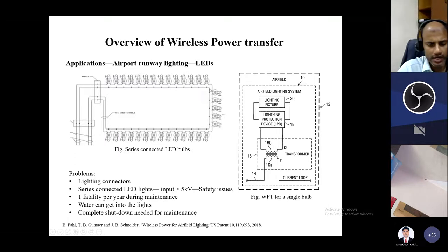An airport runway could be as long as 2 kilometers or more. On both sides of the runway there are LEDs, and the requirement is that all the LEDs be connected in series so they get the same amount of current and glow the same, which means the input voltage will be very high—given as 5 kilovolts or more. This creates safety issues when people do maintenance on the system, with a possibility of electrocution, and one fatality per year during maintenance is reported. Water can also get into the lights, along with the high voltage, and that's a problem.